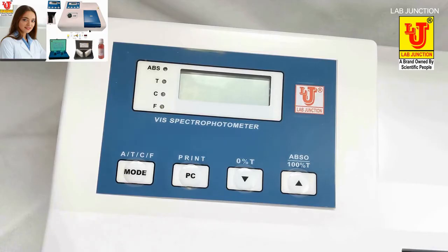In the spectrophotometer, a prism or grating is used to split the incident beam into different wavelengths. By suitable mechanisms, waves of specific wavelengths can be made to fall on the test solution. The bandwidth of the incident light can be as low as 1 to 2 nm. The spectrophotometer is useful for measuring the absorption spectrum of a compound, that is, the absorption of light by a solution at each wavelength.